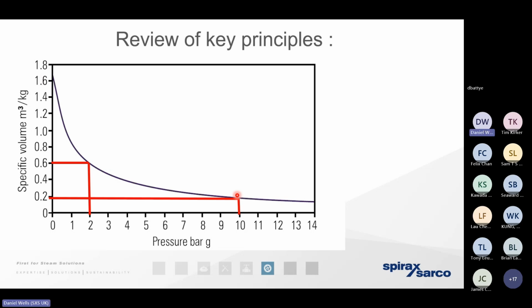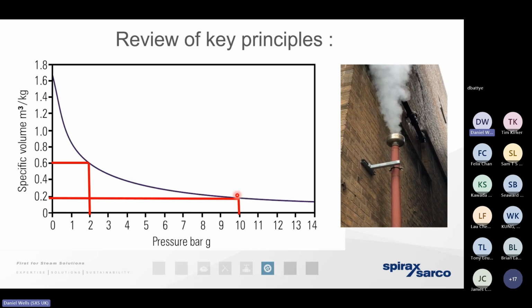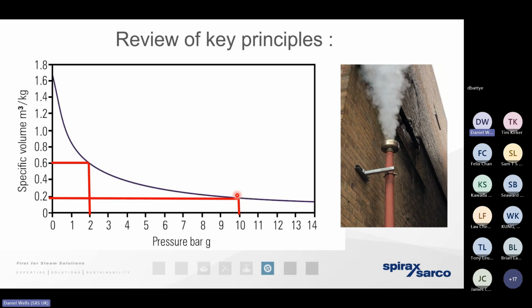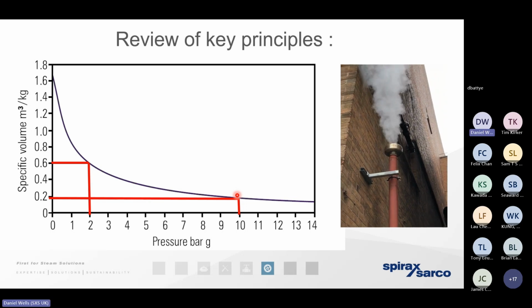Now, what we need to remember is that in previous weeks we've discussed how steam traps can and will fail, especially if they haven't been sized, selected, installed, or maintained correctly. But when we get a failing steam trap, it means we're going to have pressurized steam that could fall in pressure as it moves across the trap. And that could expand to a factor that we don't understand or can't control. That's going to want to expand into a much smaller infrastructure because, after all, condensate as a liquid is a single phase, non-compressible fluid. So if that steam expands into a very, very small infrastructure, we're going to get a huge expansion that we can't control, that will result in a lot of damage. And that's one of the reasons why we need so many of those steam vents that we've mentioned previously.